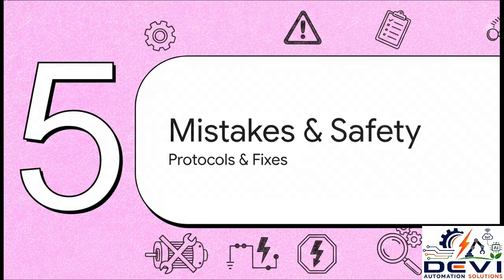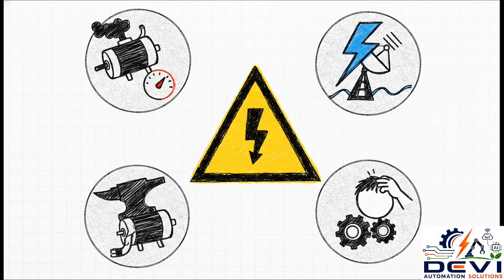Moving on to Section 5, Common Mistakes and Safety. Okay, we have to talk about mistakes, because the research highlights that getting this wrong carries extremely high costs. Wrong product selection is obvious, but incorrect parameter setting is a huge one. Literally, telling the drive that the motor is a different size than it actually is can burn out your equipment in minutes. Not to mention, poor earthing or grounding creates electrical noise that can completely ruin communication signals across your entire factory floor. And of course, overloading the drive beyond its rated capacity is just a guaranteed way to bring production to a grinding halt.